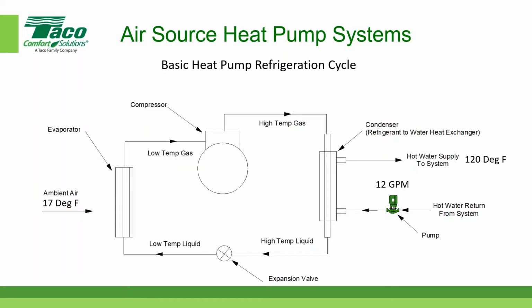So let's get into a basic diagram of what I refer to as the basic heat pump refrigeration cycle. Now this is an air to water heat pump, and it's made up of these components. One of the major components is a compressor. I'm pointing to that right now. And modern compressors are variable speed. In terms of most of the new air to water heat pumps that are available in the market today, they are variable speed compressors. And the piping that connects the compressor to the rest of the system is filled with a refrigerant. And I believe the refrigerant that is most common today is 410A.